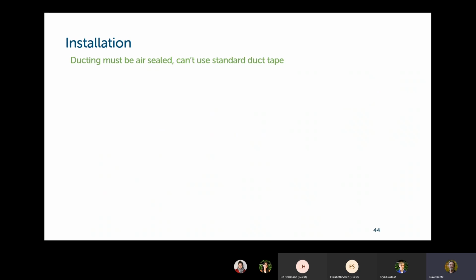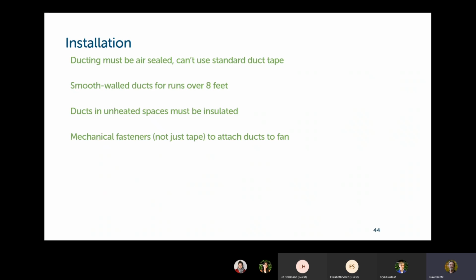There are some requirements for installation. Ducting must be air sealed, and you have to air seal it without using duct tape. For those of you who don't know, duct tape was never intended for sealing ducts. The name is an error, and it is particularly poor material for sealing ducts. You shouldn't use duct tape on ducts. You need smooth walled ducts for runs over 8 feet. You're not allowed to use corrugated stuff for longer runs. Ducts in unheated spaces, like through an attic, have to be insulated. You have to use mechanical fasteners to attach ducts to the fan. Most tapes are not durable enough for this.